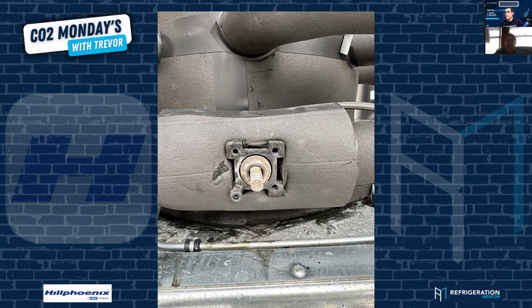Okay, next picture. Yeah, this was one of our older liquid line valves. We don't know why the contractor was taking it apart here, but we left it in there. Here's an issue. Say you got to shut that system down in an emergency. How are we closing that valve? Exactly. You got to leave that on there.